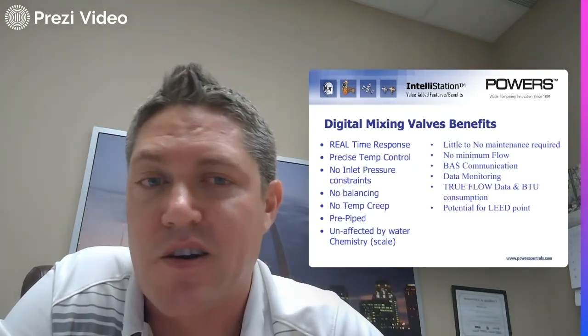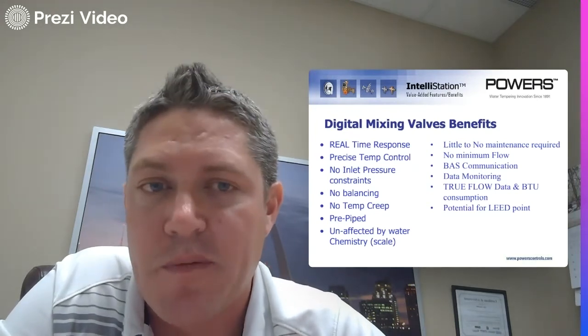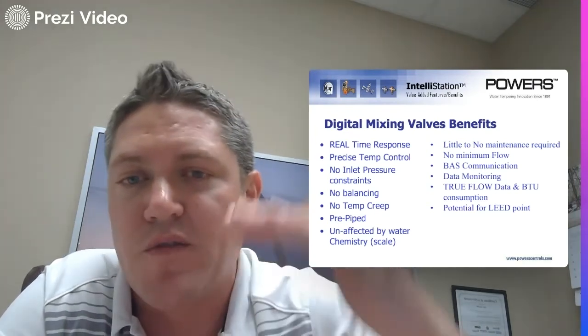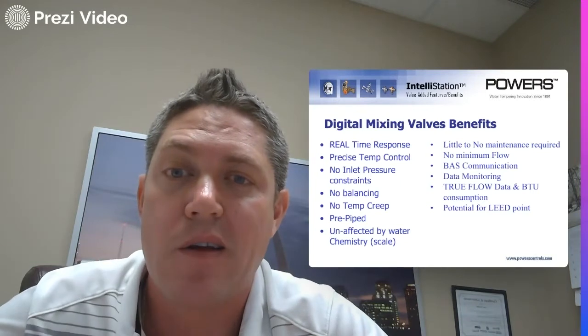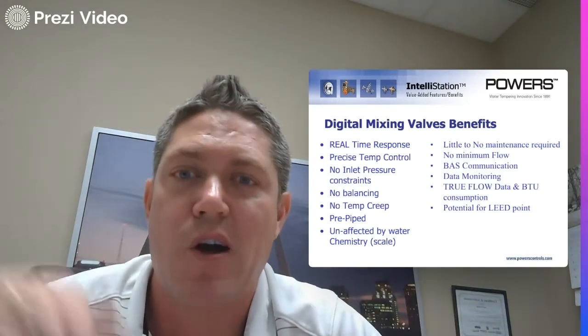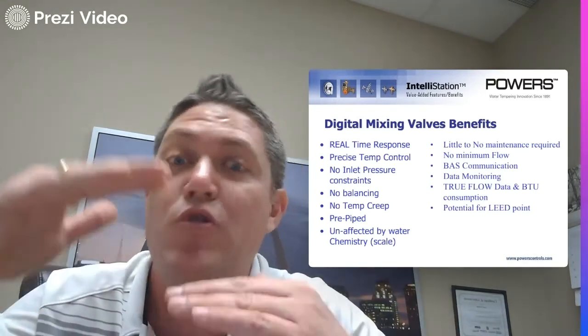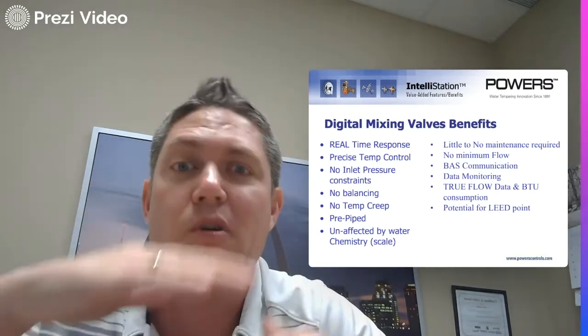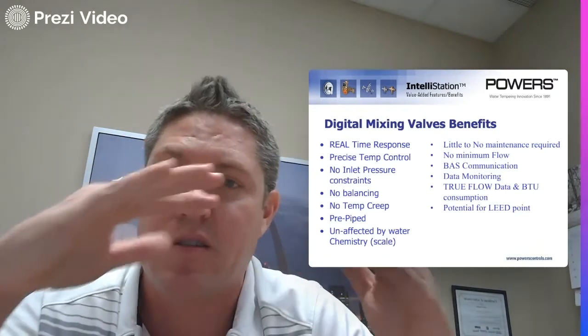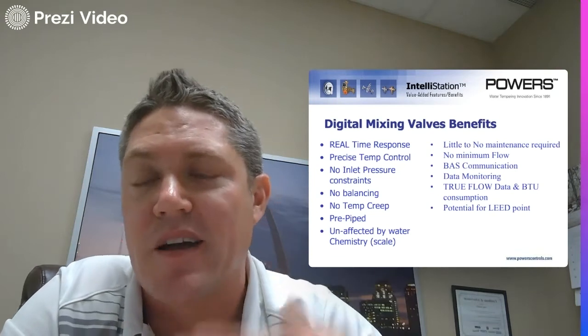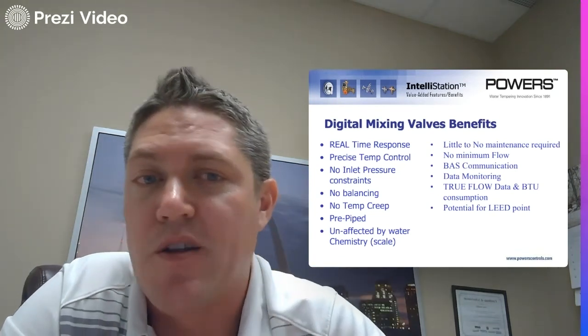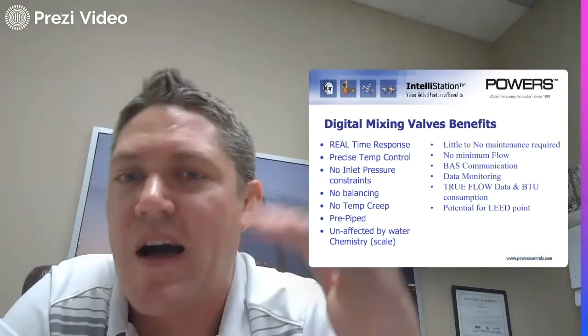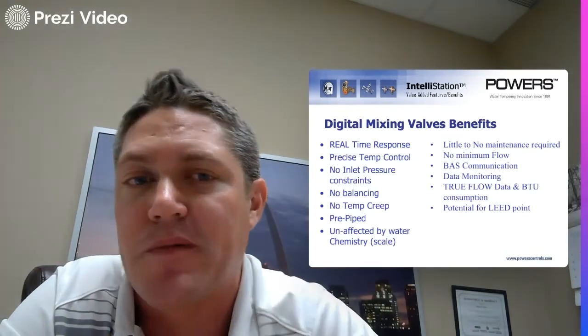So because there is such a low minimum flow rate on digital, there's no need for a 2-valve system, unless you're talking about a ton of flow where you've got to have a 2-inch system or a 3-valve system, all 3 valves 2-inch, that accommodates extremely high flow rates. But no 2-valve system is needed to accommodate the minimum flow rate.